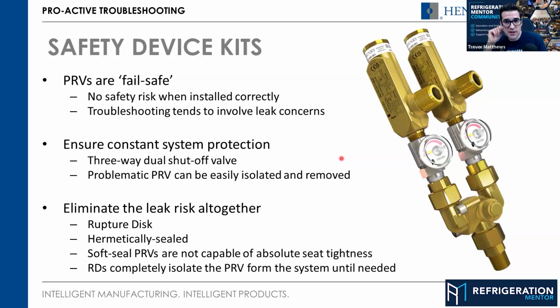I do have someone who asked the question, can these be repaired? Yes and no. Again, typically, nothing straightforward. None of our valves are designed to be repaired. All of our valves are sealed once they leave the factory, and you can't replace the components. You do get typically larger industrial valves, in North America under the ASME code, where there's a stamp that says you're an official ASME valve repair maintenance laboratory, licensed to repair the valves. But with our valves, no, they're all one-use items.